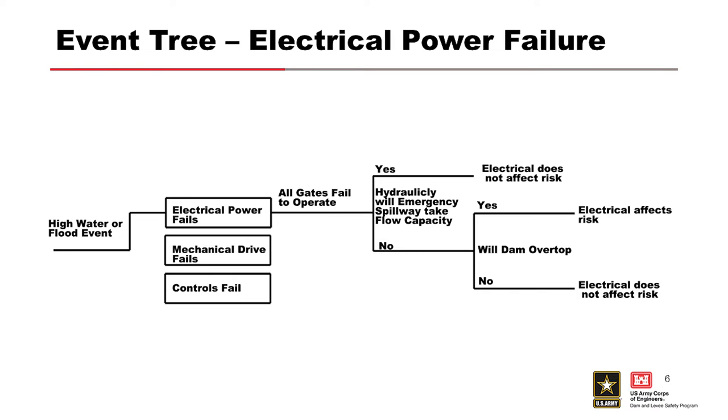All those need to be looked at in this case. So, this event tree, first event, you have a high water flood event, electrical power fails, that causes all gates to fail to operate. Then you ask the question, is it hydraulically, will the emergency spillway gate take the flow capacity, yes or no? If yes, then the electrical does not affect the risk.